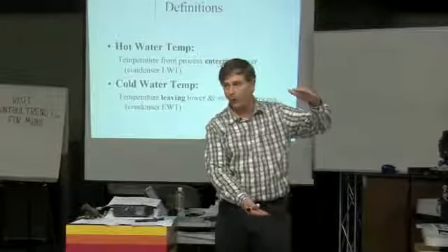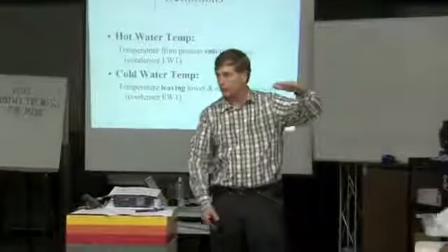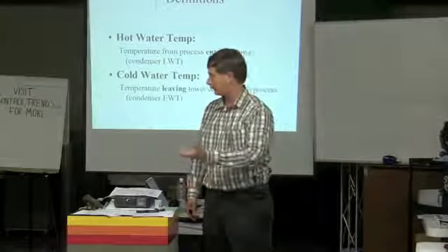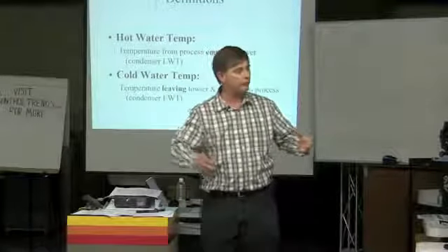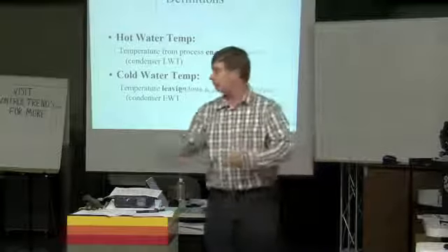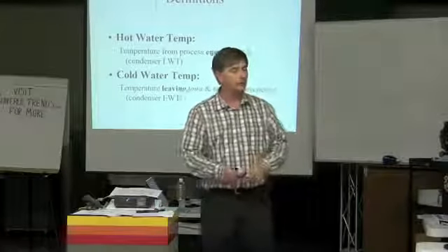If you've just got 1 pound of pressure trying to push through that equalization tube, it's not a whole lot of force. And so when you're trying to pack 900 GPM through a tower and you're trying to equalize a basin, everything needs to be nice and clean.